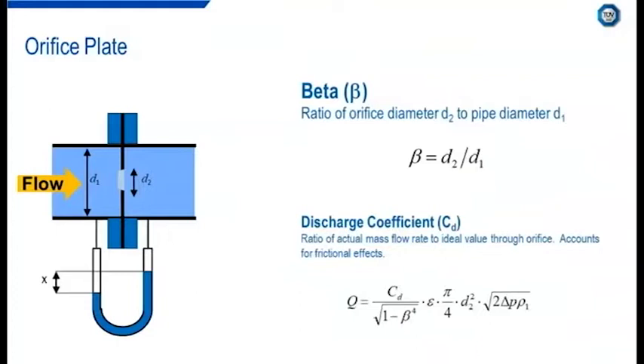Differential pressure meters operate by partially obstructing the flow. They all operate on the same basic principle: partially obstructing the flow, which then creates a difference in the static pressure between the upstream and downstream of the device. The beta ratio is the ratio of the pipe diameter, denoted here as D1, and the diameter of the obstruction, D2, the diameter of the orifice in the case of the orifice plate.